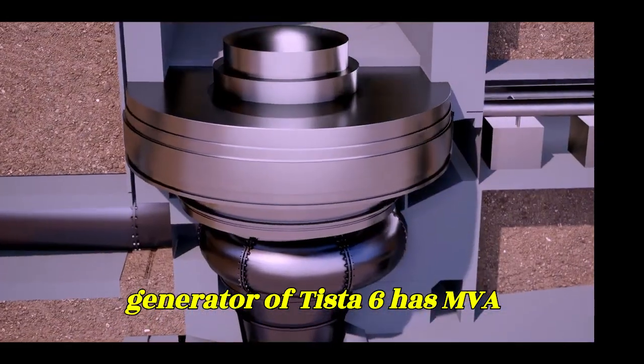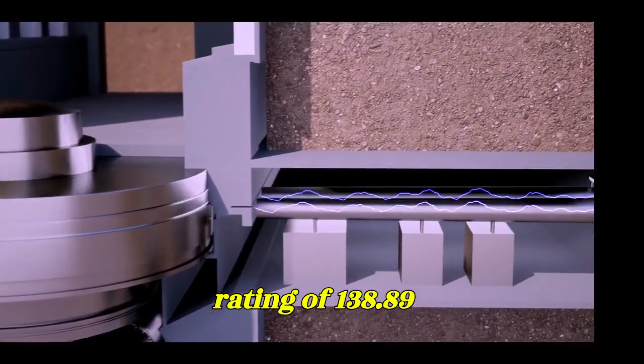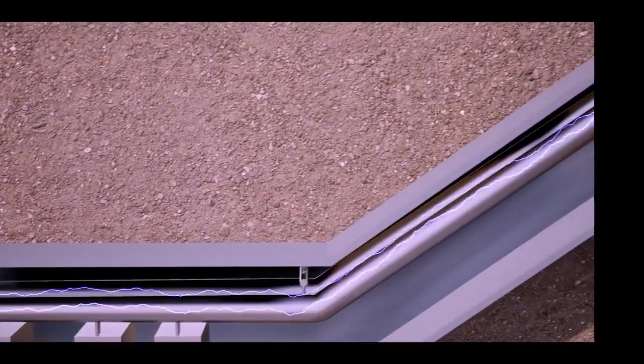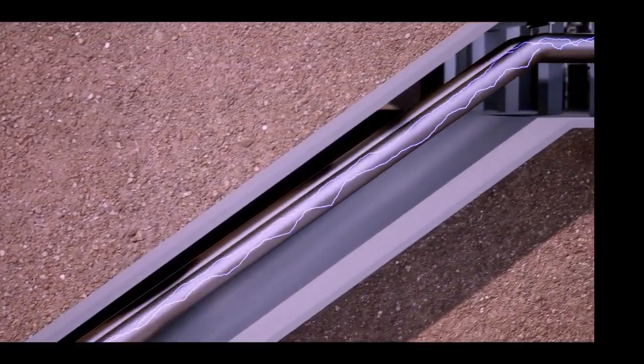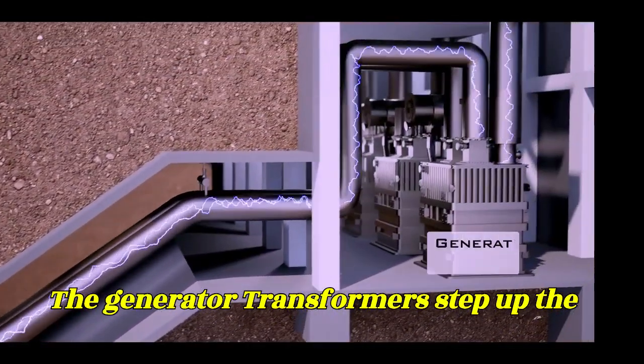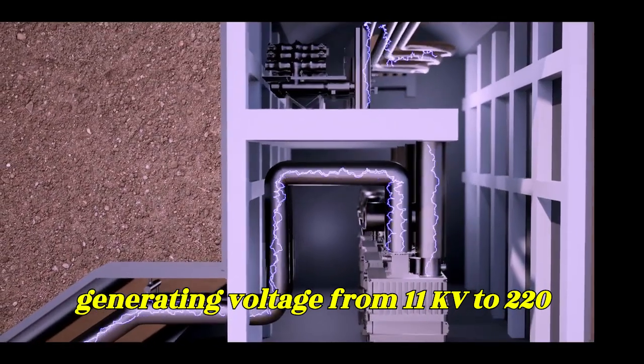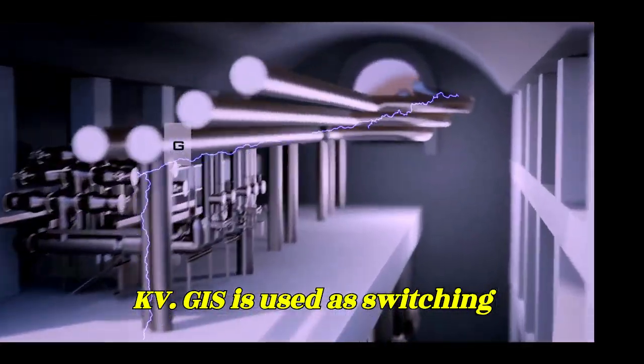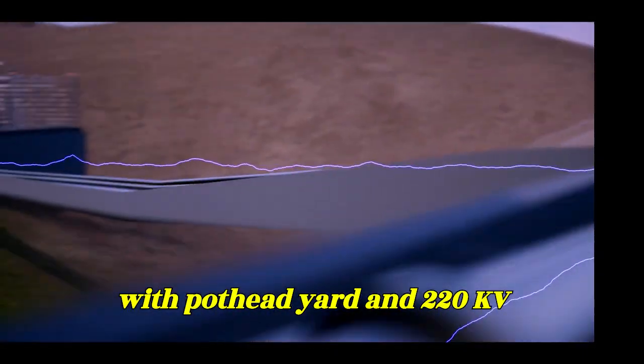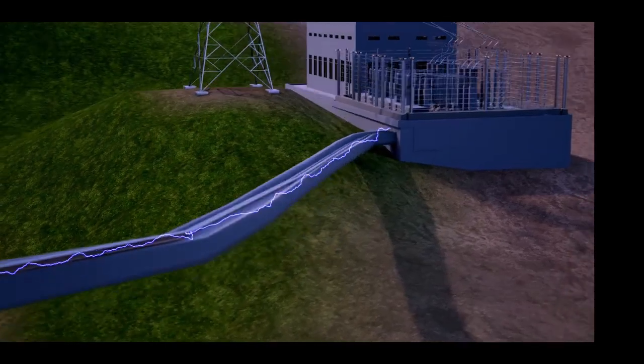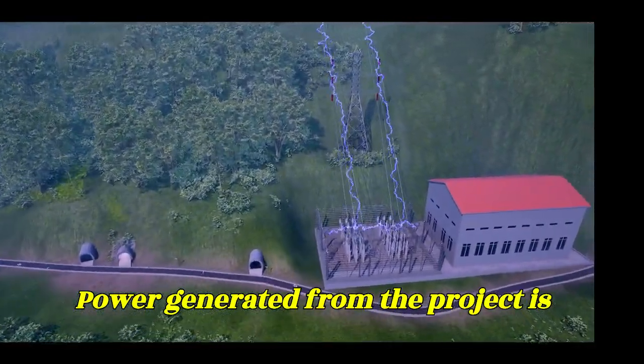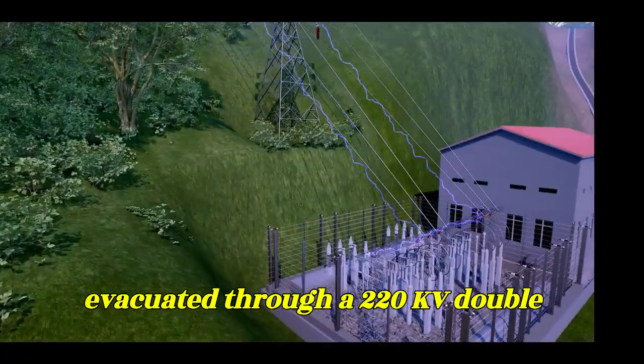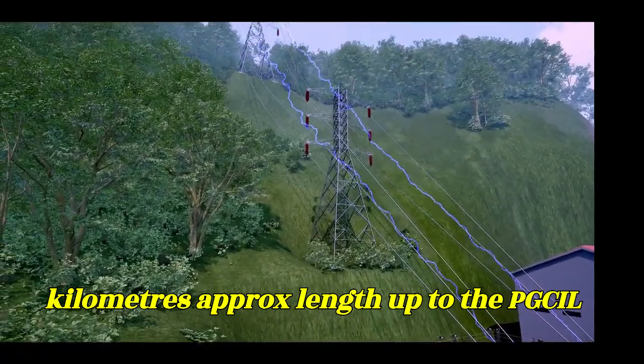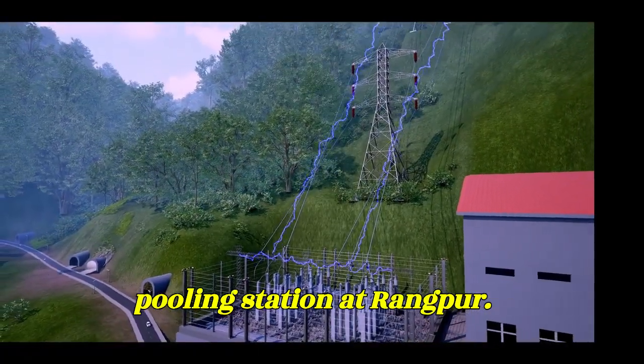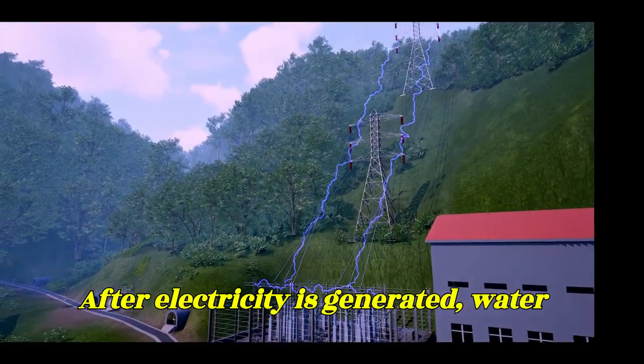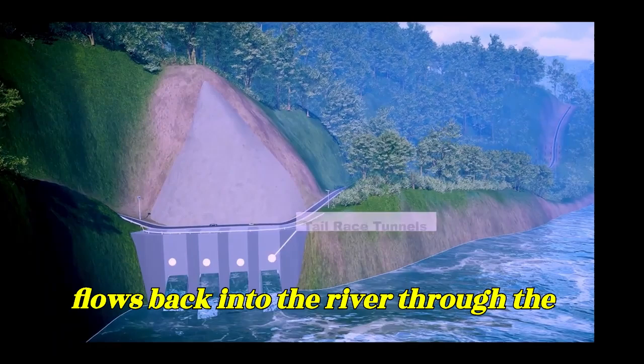The generator of Teesta 6 has an MVA rating of 138.89 and the generating voltage of 11 kV. The generator transformers step up the generating voltage from 11 kV to 220 kV. GIS is used as switching system to connect the generating units with pothead yard and 220 kV transmission lines. Power generated from the project is evacuated through 220 kV double circuit transmission lines of approximately 12.5 km length up to the PGCIL pooling station at Rangpo. After electricity is generated, water flows back into the river through the tail race tunnels.